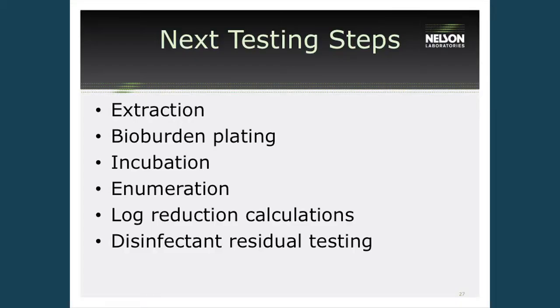So the next steps in this process are very similar to the bioburden process: we are extracting the device and performing the bioburden testing. Then after that, the plates are incubated, enumerated, and log reductions are calculated. Disinfection residual testing is also extremely important for the disinfection validation. This is to make sure that there are no residuals of detergent or disinfectant left on the device after this process.